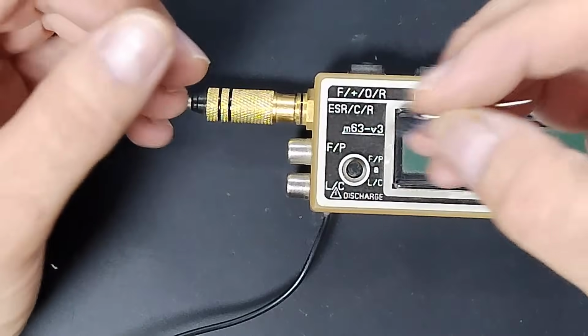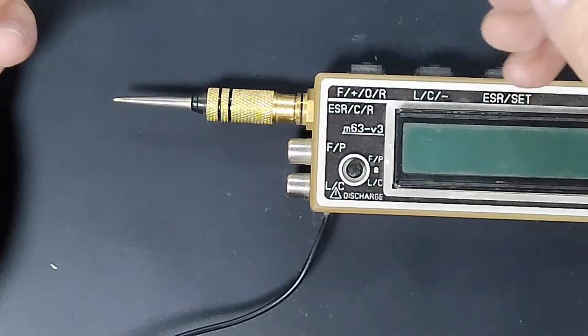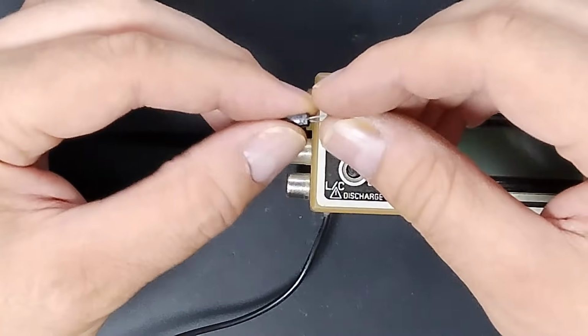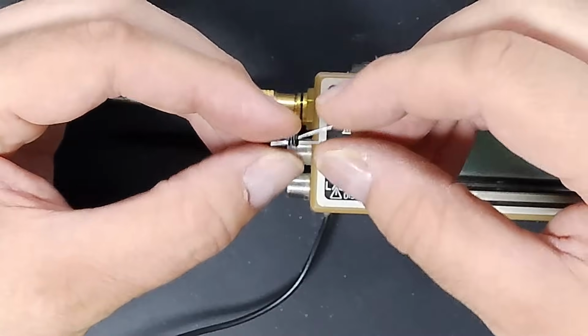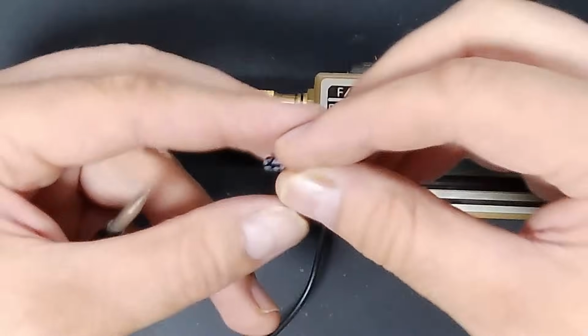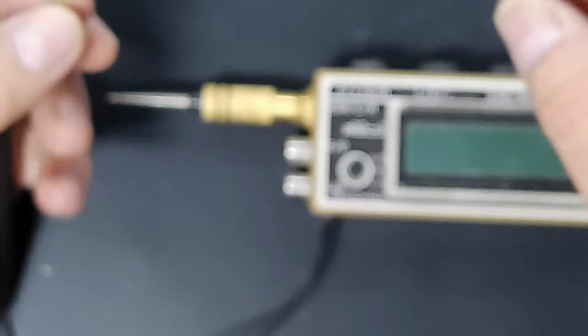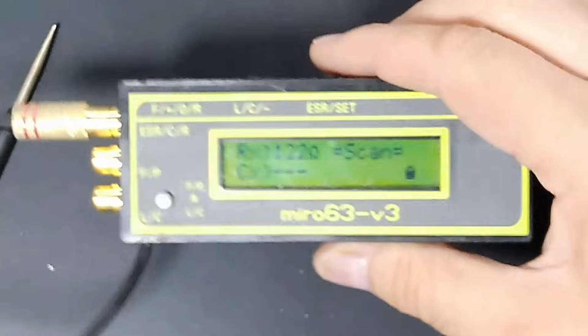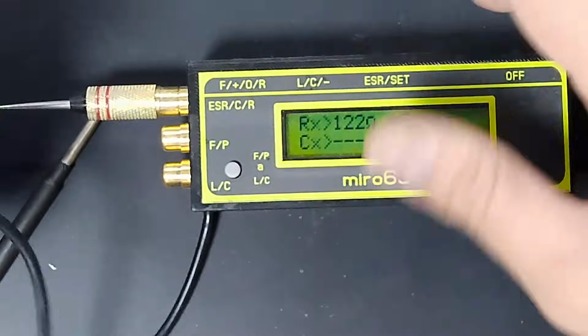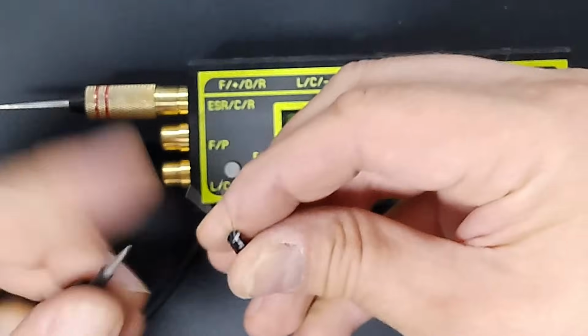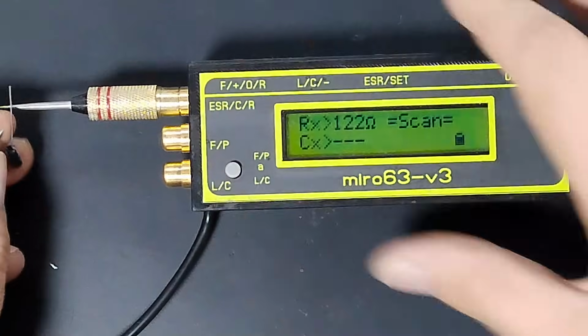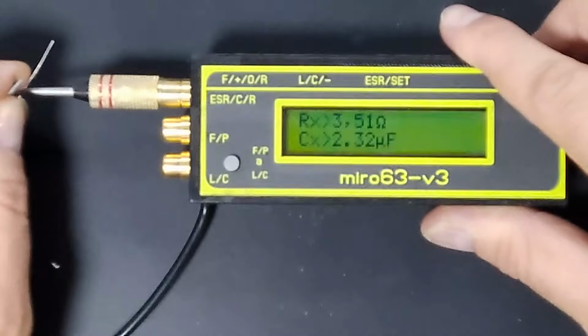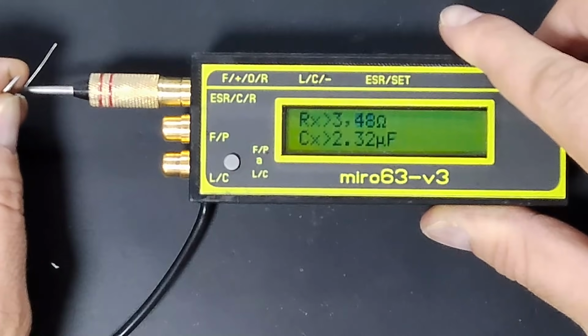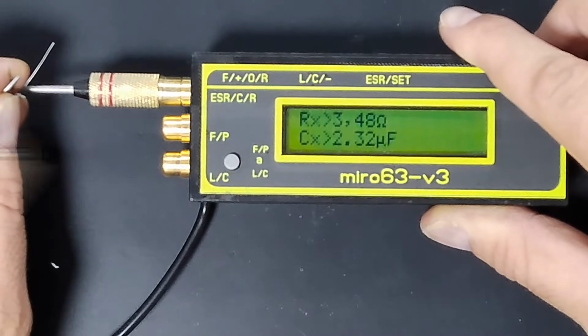They say you need to use a calibrating capacitor between 470 nanofarads and 4.7 microfarads. I don't have a precision capacitor in this range, so I need to test it with this tester to make sure I have a reference value, then calibrate the other tester to read the same. I have 2.32 microfarads.